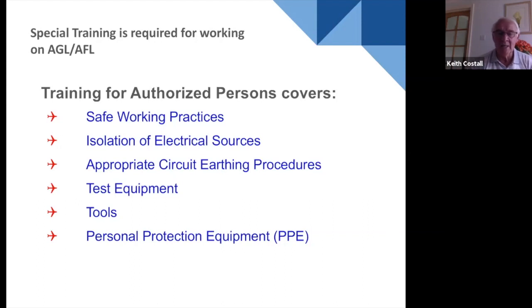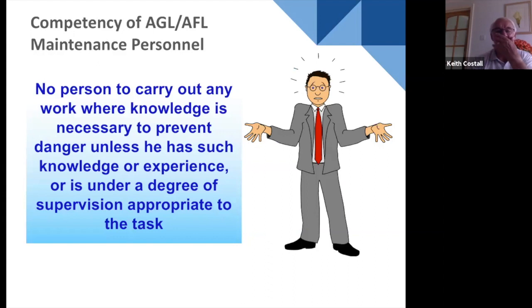We need to isolate. We need to be able to earth the system down. In AGL, we have kilometers and kilometers and kilometers of primary cable that, when it's operating, is just like a big capacitor. So even if we switch off a CCR, we have still got an electrical charge there. We need to be able to operate the test equipment and tools correctly, and as I said, have the correct PPE.